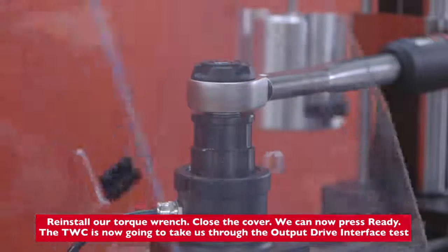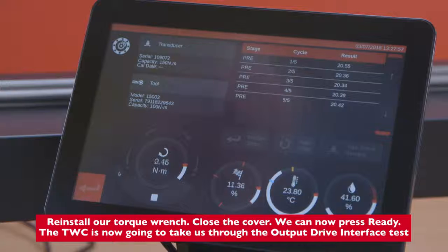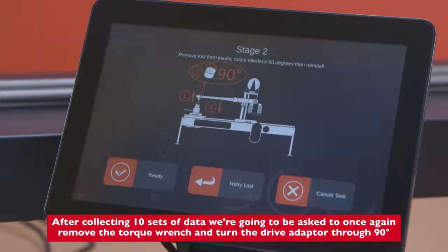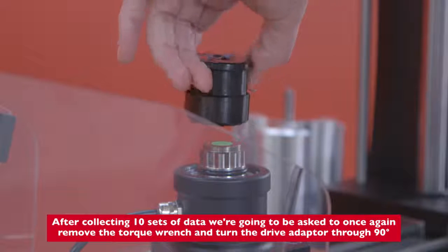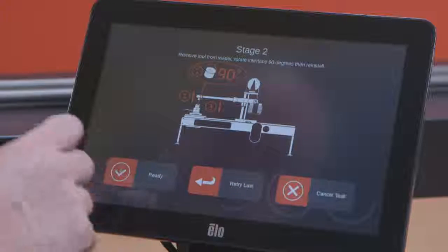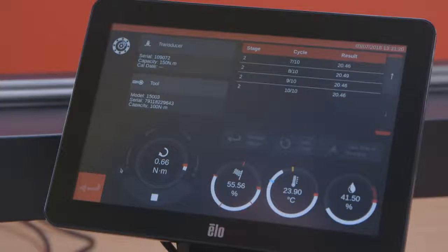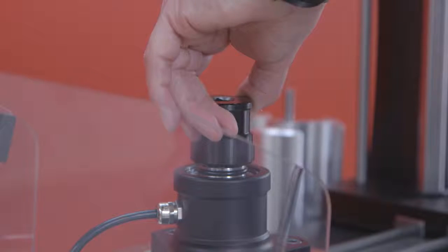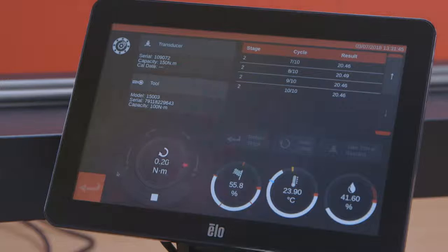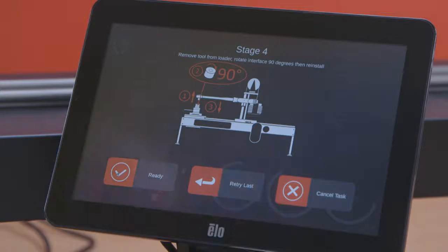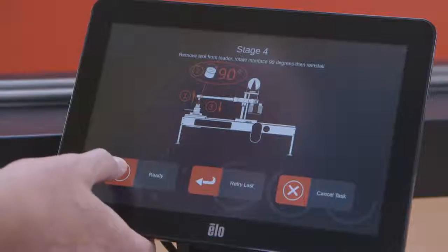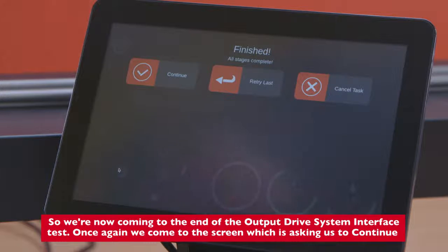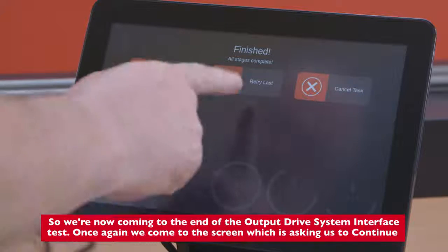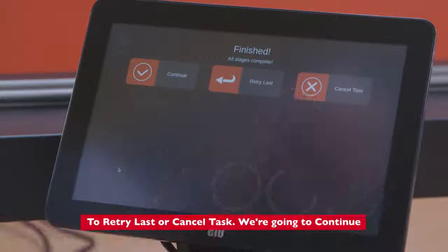Reinstall our torque wrench, close the cover, and we can now press ready. The TWC is now going to take us through the output drive interface test. After collecting 10 sets of data, we're going to be asked to once again remove the torque wrench and turn the drive adapter through 90 degrees. So we're now coming to the end of the output drive system interface test. Once again we come to the screen which is asking us to continue, to retry the last, or cancel that task. We're going to continue.